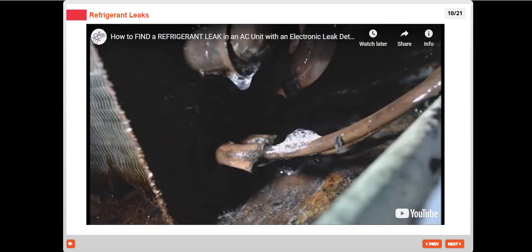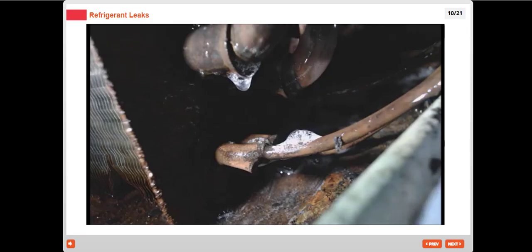So right here is an up-close image with the bubble leak detector. I actually have a couple of leaks on this system, where the distributor tubes attach into the evaporator coil. And you can see the bubble action right there, it's making tiny little bubbles and it's kind of foaming. So that's what you're looking for, and that'll pinpoint your leak.